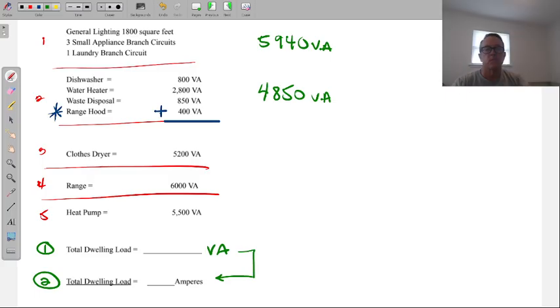And you would have multiplied by 75%? The reason you don't do that in this situation is because there has to be 4 or more, but they all have to be above 500 watts, but you got one at 400. So then you don't use that one.